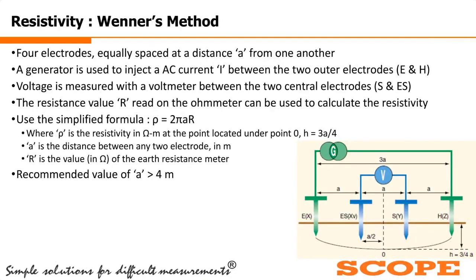Then the next one is resistivity measurement using Wenner's method. In this soil resistivity measurement, we are not connecting any earth electrode. Here we are measuring the soil resistivity, so that we can do a survey of the soil and build our earthing network. To do that soil resistivity survey, we use Wenner's method.